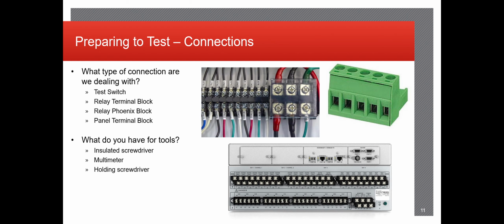So, prepping your test for your connections, there are a lot of different ways you can hook up to the relay. The easiest way I've found is if there are test switches available that hook up directly to the back of the relay. These test switches usually hook up to both the inputs and outputs as well as all the voltages and currents. This is the easiest way to set up because the relay test set you're utilizing will sometimes have plugs that you can just shove right into the knife blades once they're all opened, and from there you can just plug in your cables to wherever you need them to go to the relay.